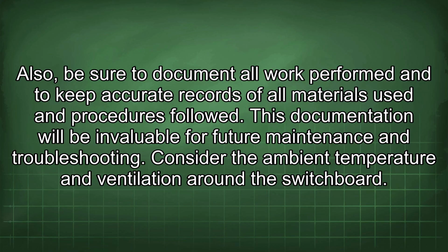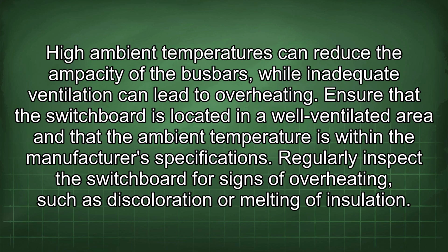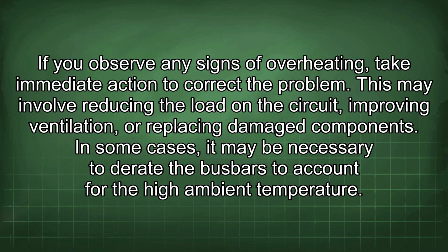Consider the ambient temperature and ventilation around the switchboard. High ambient temperatures can reduce the ampacity of the busbars, while inadequate ventilation can lead to overheating. Ensure that the switchboard is located in a well-ventilated area and that the ambient temperature is within the manufacturer's specifications. Regularly inspect the switchboard for signs of overheating, such as discoloration or melting of insulation. If you observe any signs of overheating, take immediate action to correct the problem. This may involve reducing the load on the circuit, improving ventilation, or replacing damaged components.